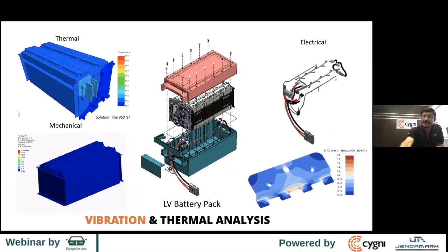So it's important to make sure it is designed by construction. And the role of BMS, the battery management system - this is one area where India needs a lot of focus and attention, because today, as had happened with solar, you have a lot of dumping of both BMS, which are imported protection boards, as well as low quality cells. This results in two things. One, these protection boards are very rigid - they do not have multiple means of measuring temperatures from the battery pack. Their upper and lower cutoffs are fixed, which means it does not take into account the dynamism of the battery pack itself.